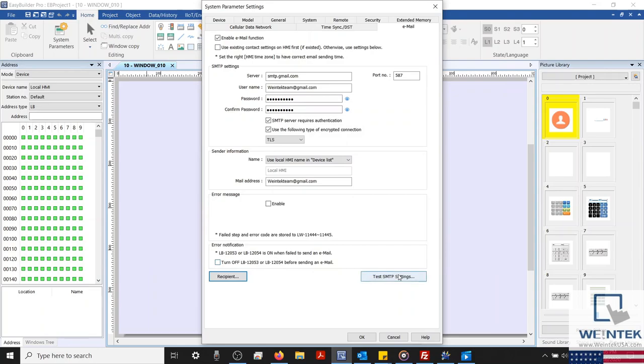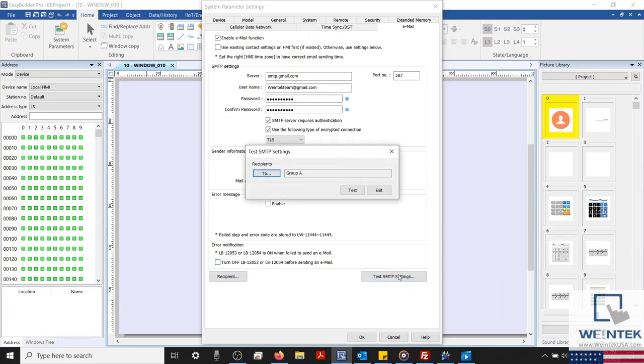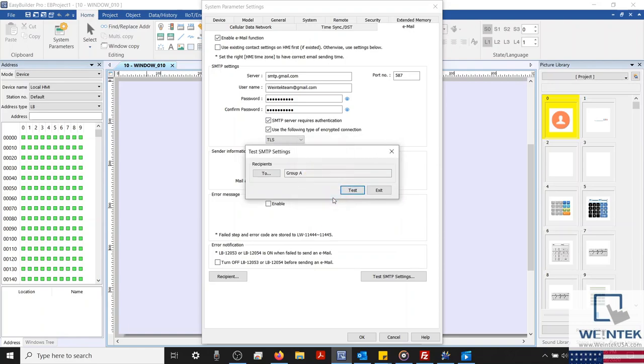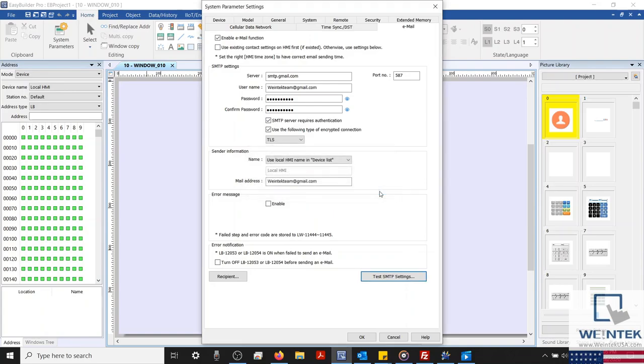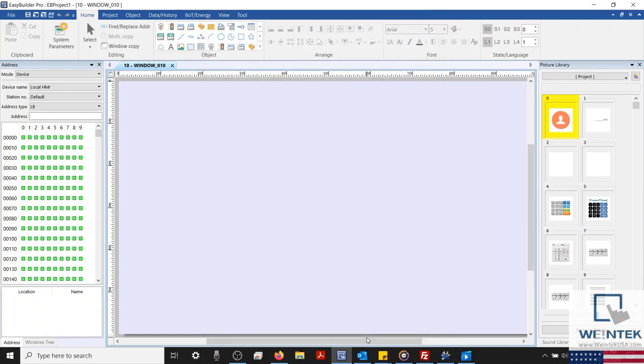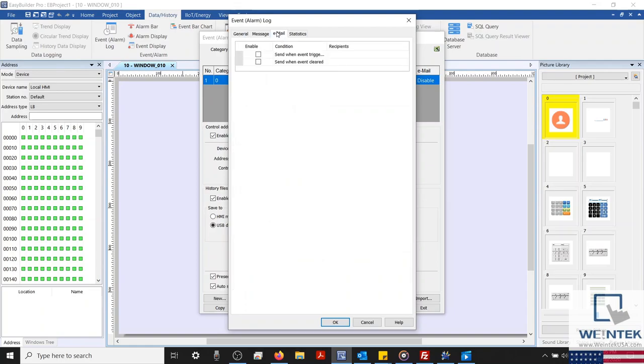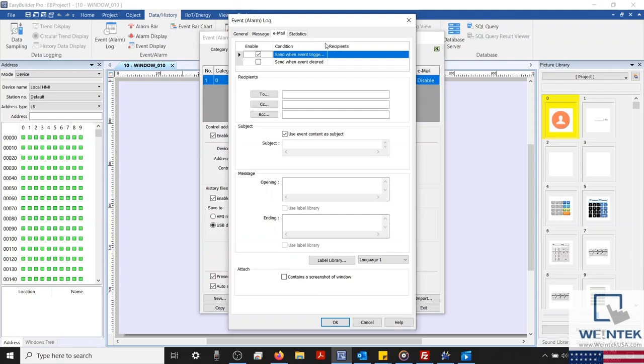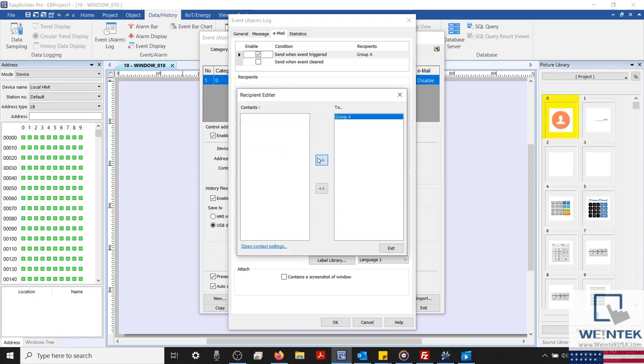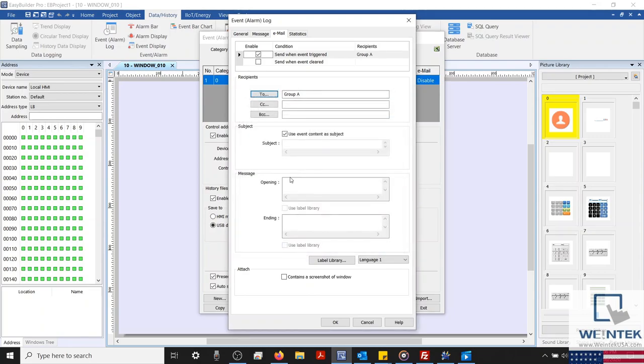And with my SMTP settings configured, I'm going to add myself as a recipient into Group A. And before we exit, let's test our SMTP settings. And with our settings properly configured, we'll head back to our event's settings menu and enable an email push notification. Our alarm will send an email when the event is triggered. We'll send this email to Group A. And I'll configure the HMI to attach a screenshot of our display as well.